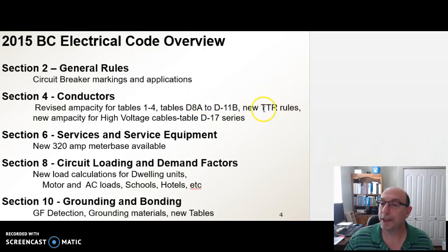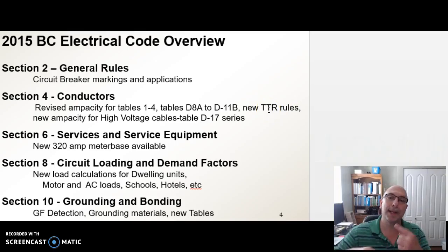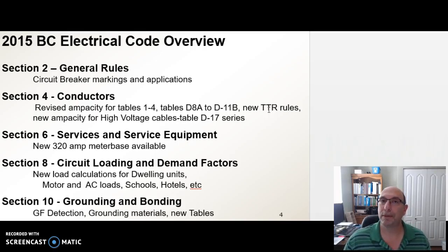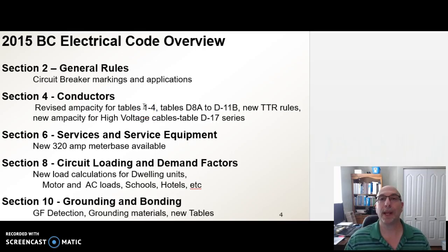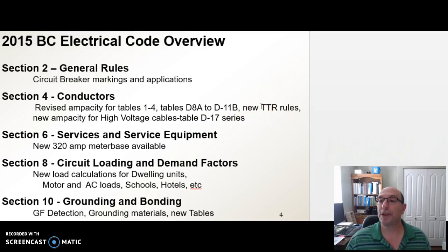There's a big change for the temperature terminating rating rule, which came out in the last edition. We've now harmonized with the Americans — we've gone a little backward, but we've harmonized. If you have a piece of electrical equipment rated for less than 100 amps, you must default to the ampacities of Tables 1 through 4 in the 60-degree ampacity column. And if it's above 100 amps, then you can use the 75-degree rating ampacity column.